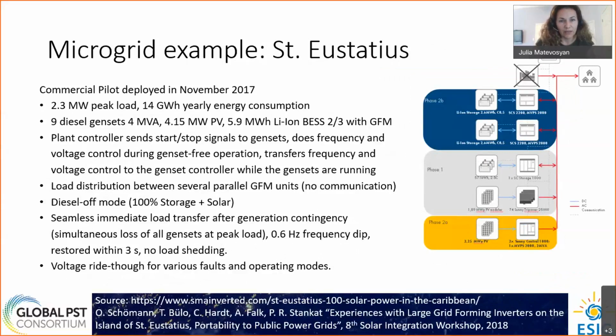Another example is the microgrid in St. Eustatius. SMA actually deployed a number of microgrid types of projects on a number of islands, but this is one of the ones on which information is more widely available. The peak load of the island is 2.3 megawatt. Yearly energy consumption is 14 gigawatt hours. Initially, the island was powered by 9 diesel gensets, which makes power supply very expensive. At some point, 4 megawatts of solar was added, and a 1 megawatt battery, which was a grid-following battery, and then as a second phase, an additional over 2 megawatt of grid-forming battery was added.